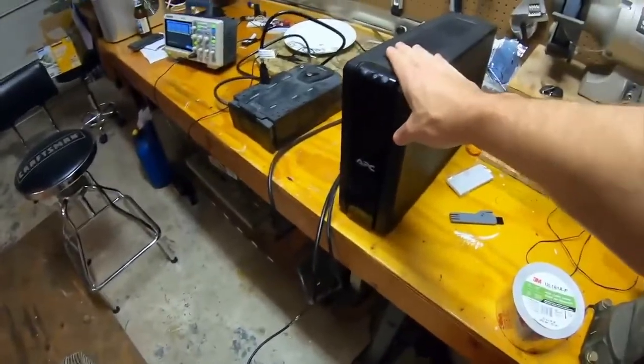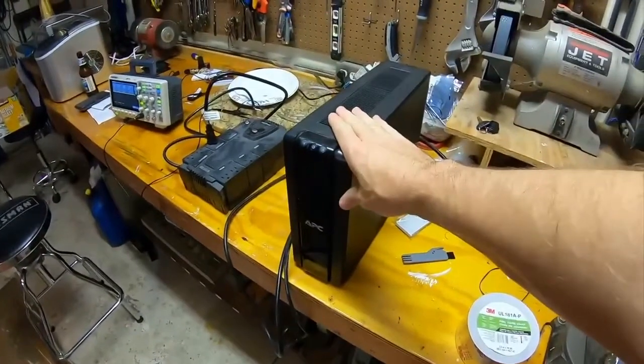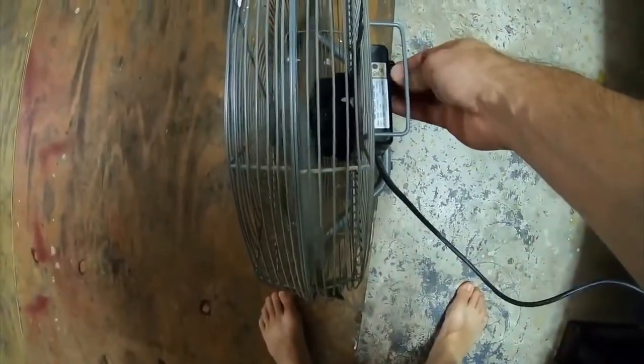It's not in battery backup mode right now. Remember, this is the UPS that actually seemed to perform a little bit better. I'll turn on the fan. This should be as if the fan was running off the wall outlet, because it is.